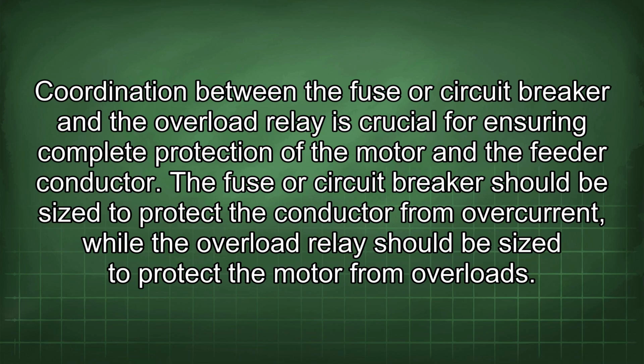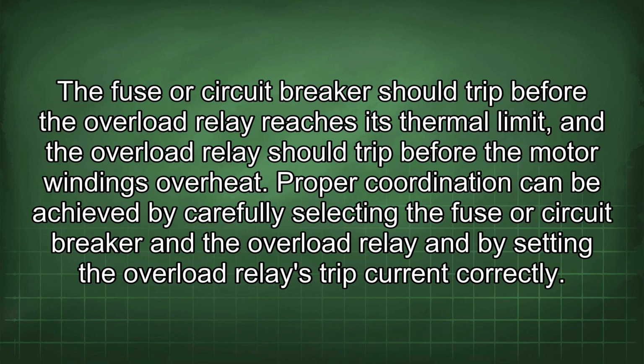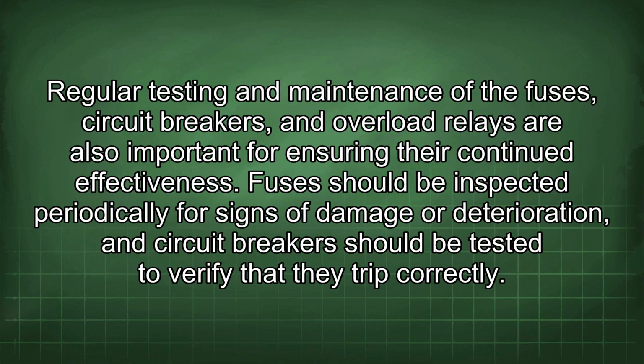Coordination between the fuse or circuit breaker and the overload relay is crucial for ensuring complete protection of the motor and the feeder conductor. The fuse or circuit breaker should be sized to protect the conductor from overcurrent, while the overload relay should be sized to protect the motor from overloads. The fuse or circuit breaker should trip before the overload relay reaches its thermal limit, and the overload relay should trip before the motor windings overheat. Proper coordination can be achieved by carefully selecting the fuse or circuit breaker and the overload relay and by setting the overload relay's trip current correctly. Regular testing and maintenance of the fuses, circuit breakers, and overload relays are also important for ensuring their continued effectiveness.